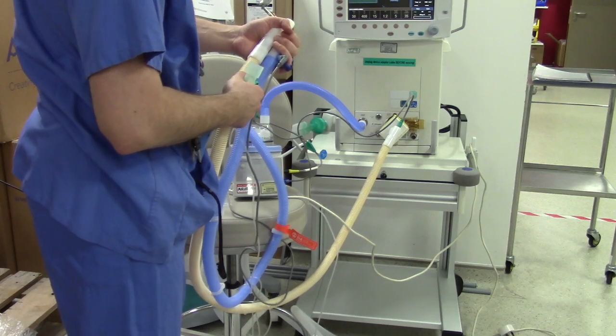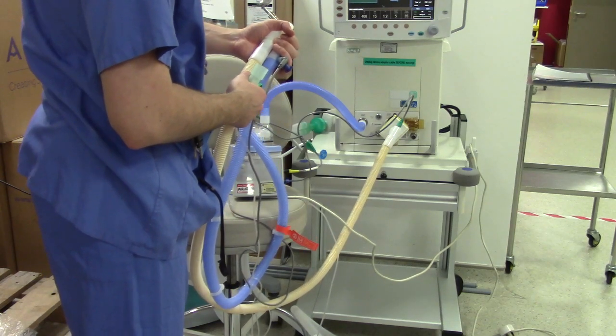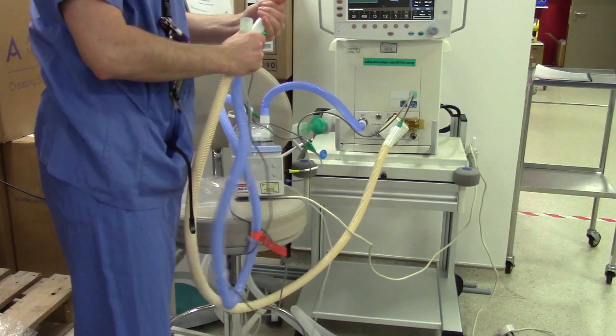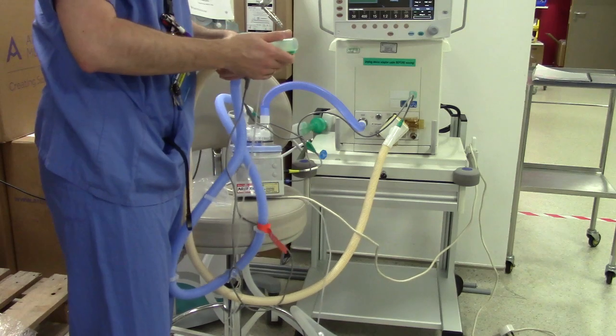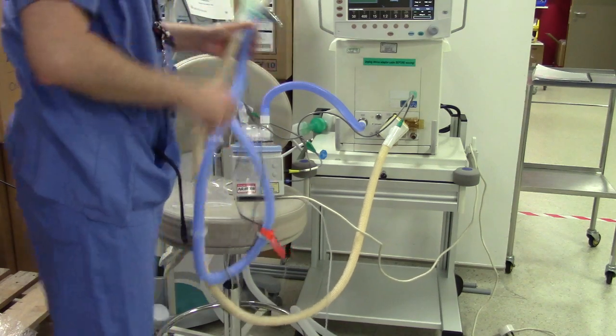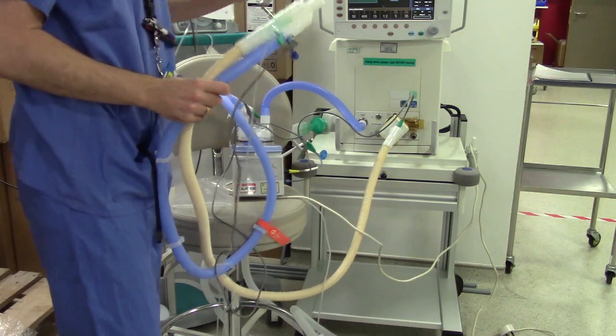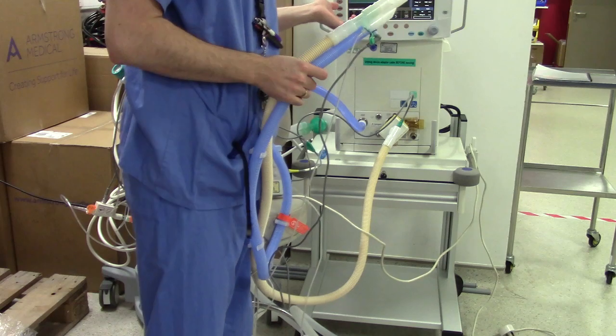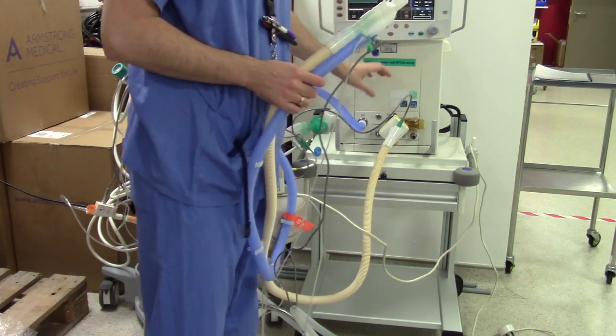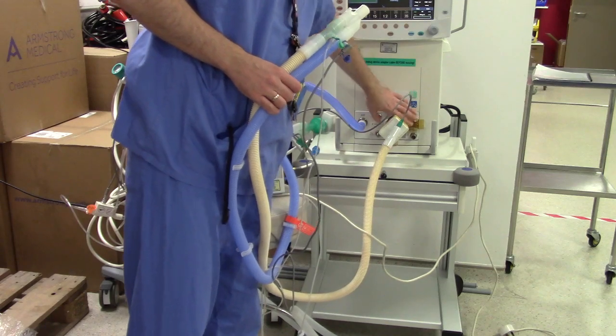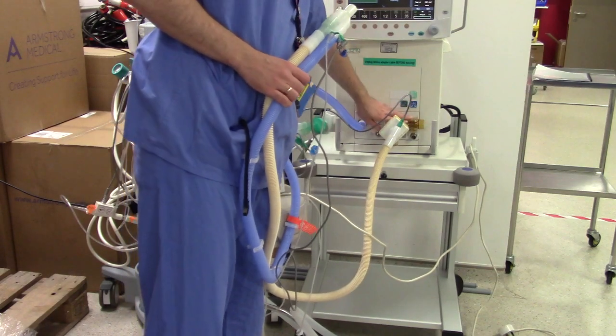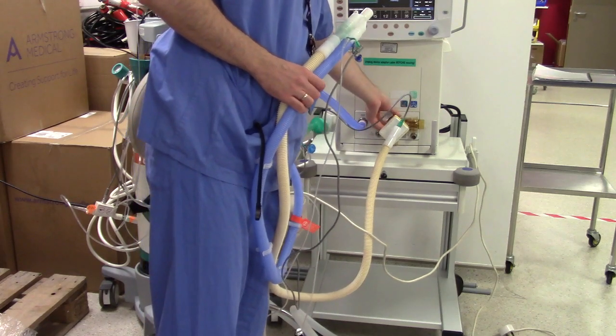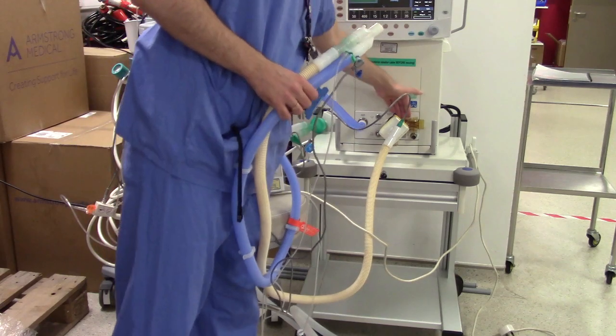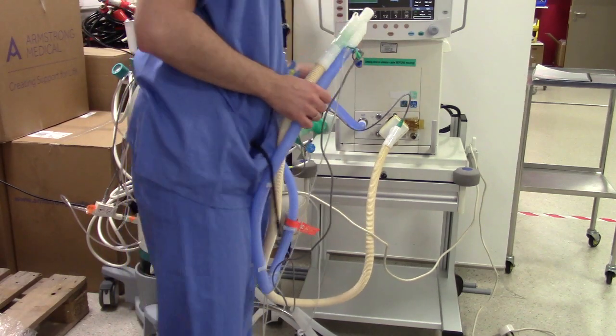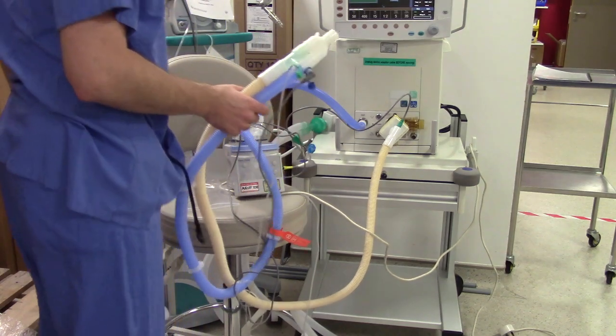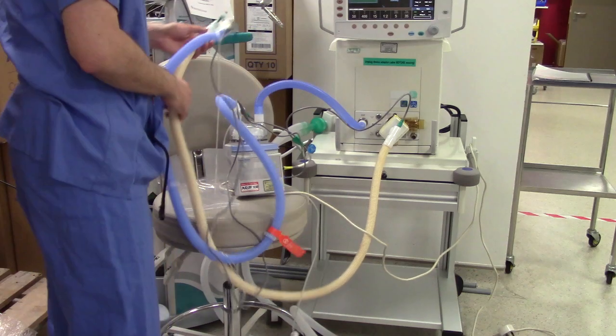Where do you connect the... Do you know which side of the circuit? The exhalation side. So in our case, this will be the white part of the circuit. Okay, so this is the setup for humidification. In some cases, when we have enough blocks, there are special heating blocks that cover this exhalation block and warm it in order to create even less condensation build-up inside the exhalation block. Okay, so that's to do with the humidification.